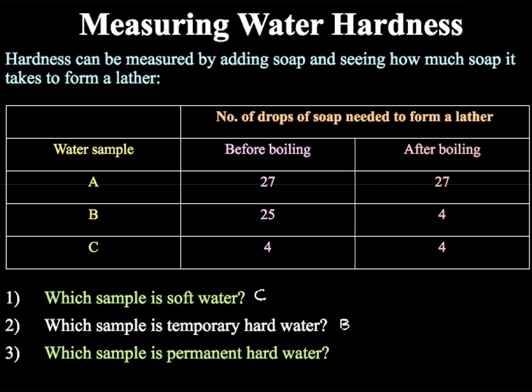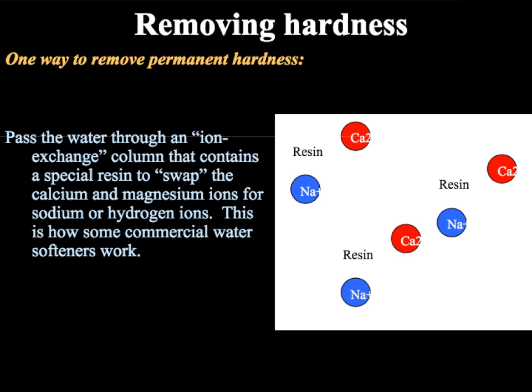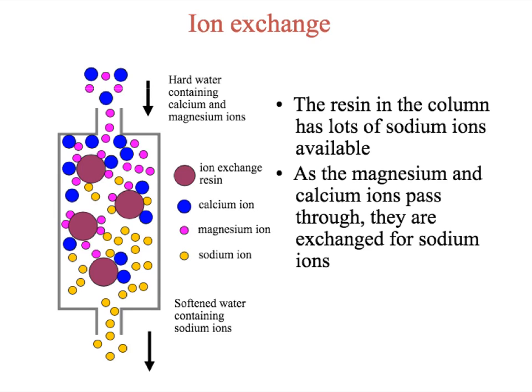Since boiling has had no effect on the hardness of sample A, in order to remove permanent water hardness we need to use an ion exchange column. This is a column that contains a special resin to swap the calcium and magnesium ions for sodium or hydrogen ions, and is how many commercial water softeners work. Inside the ion exchange column the special resin is held in place with lots of sodium ions available for exchange. The hard water containing calcium and magnesium ions enters the top of the column; those ions are attracted to the resin where they are exchanged for sodium ions, which then exit the bottom of the column with the water.